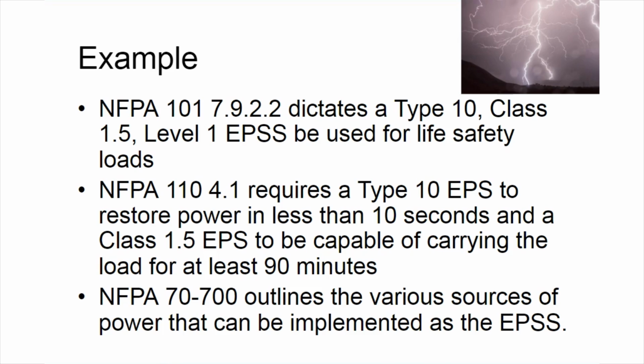So let's look at an example. NFPA 101 7.9.2.2 dictates a Type 10 Class 1.5 Level 1 EPSS for use for life safety loads. NFPA 110 4.1 requires a Type 10 EPS to restore power in less than 10 seconds and carry Class 1.5 loads capable of running for 90 minutes. NFPA 70-700 outlines various sources for power that can be implemented as the EPS.